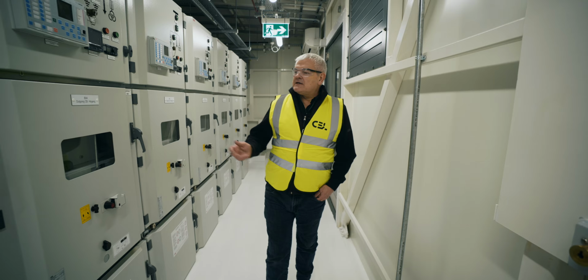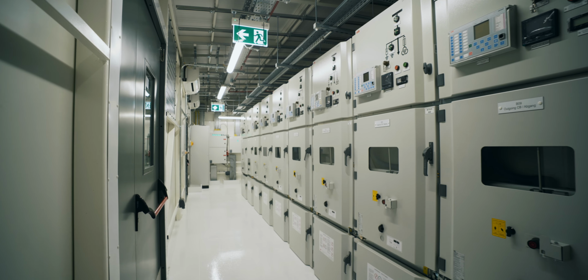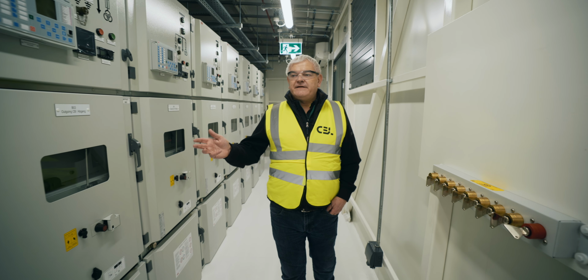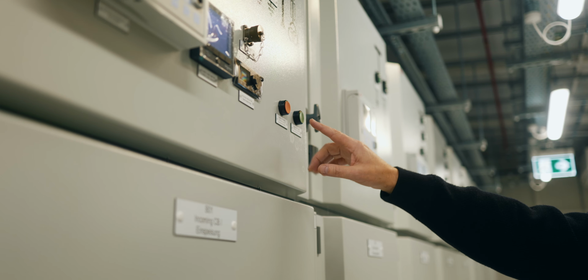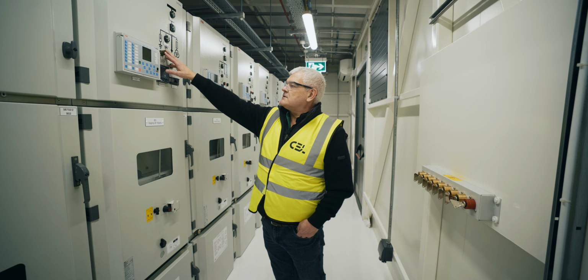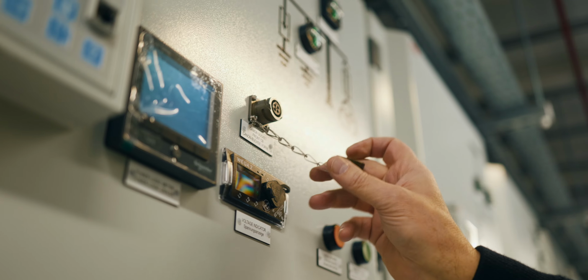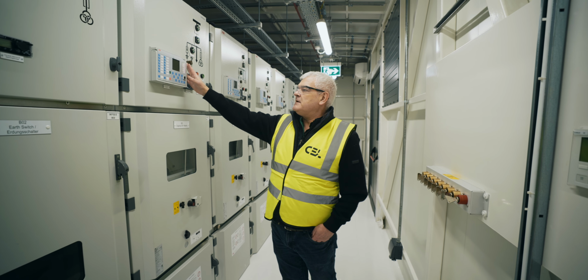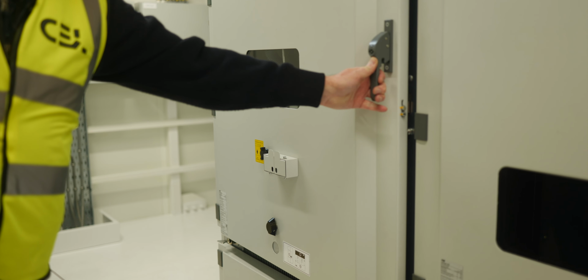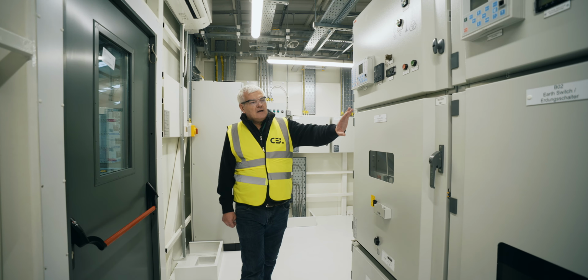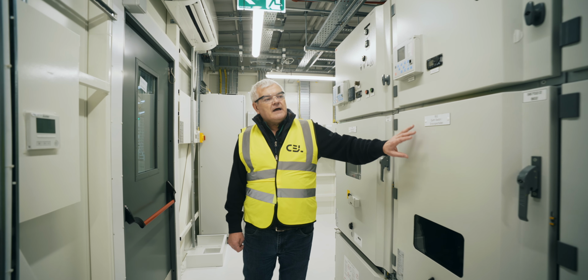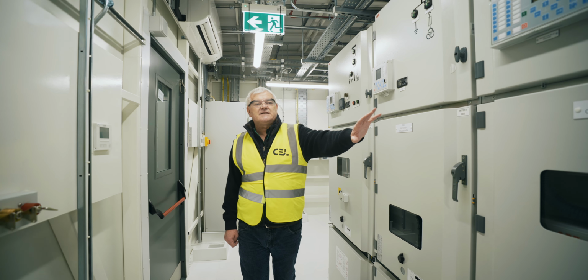This MV pod has 20 kV ABB air insulated Unigear. This has been FAT tested with the client and the customer here. Each of the breakers have a local open and close, and also have a pendant control. These are operated through the ABB relay system. So the ABB switchgear has a 2500 amp incomer, an earth switch, and then 7 outgoing ways of 630 amp.